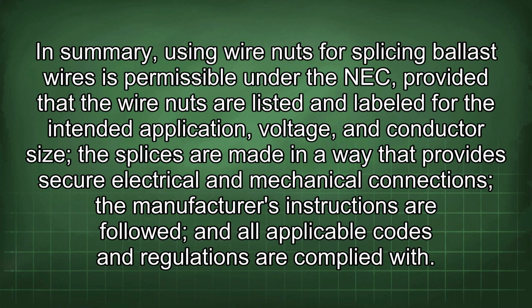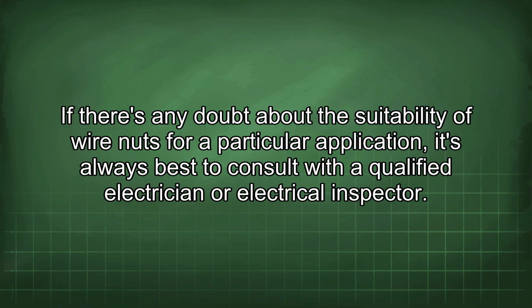In summary, using wire nuts for splicing ballast wires is permissible under the NEC, provided that the wire nuts are listed and labeled for the intended application, voltage, and conductor size. The splices are made in a way that provides secure electrical and mechanical connections. The manufacturer's instructions are followed, and all applicable codes and regulations are complied with. If there is any doubt about the suitability of wire nuts for a particular application, it's always best to consult with a qualified electrician or electrical inspector.